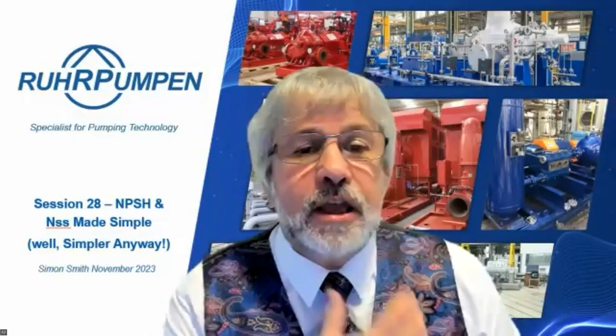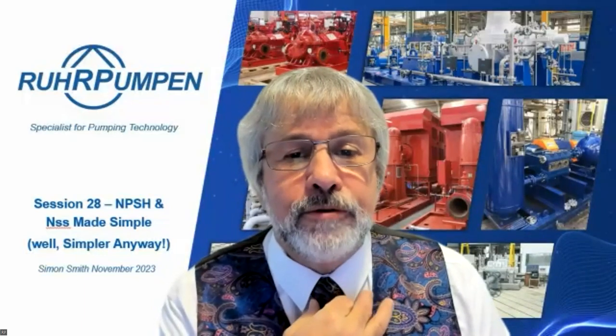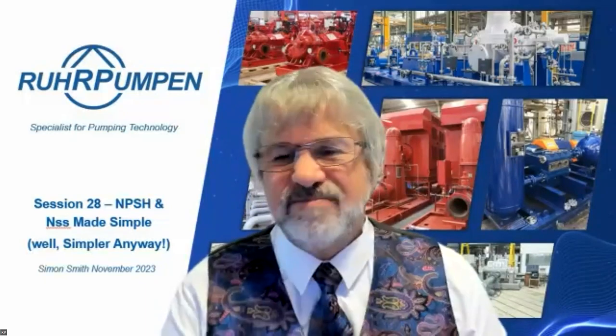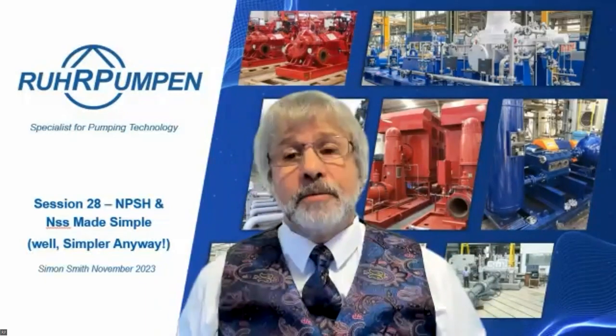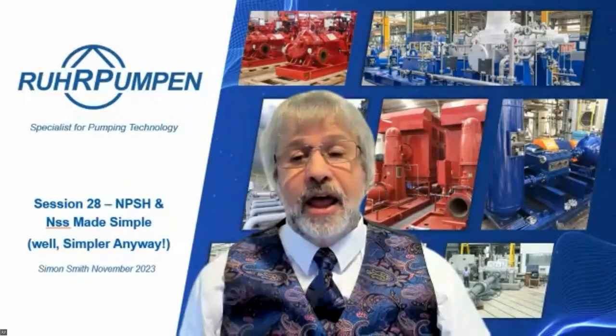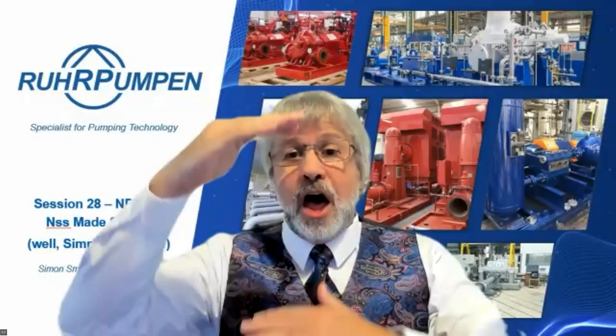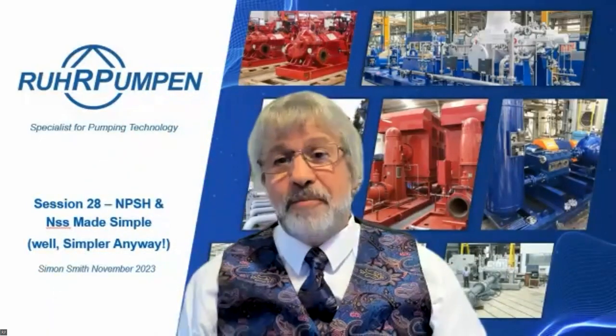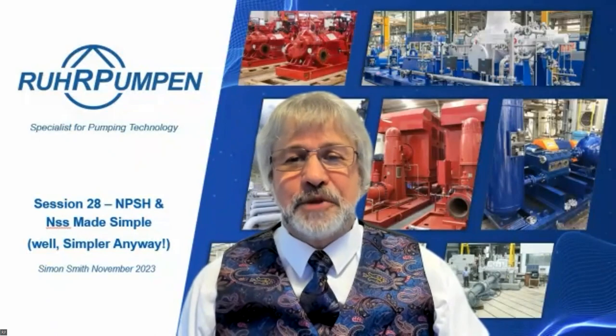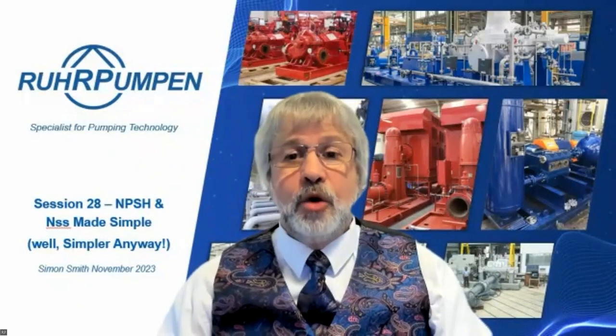Dharmesh Kumar Panchal asks about NPSH ratio versus NPSH margin. It's just two different ways of looking at the same thing. What we're looking for is to keep a nice healthy margin above the NPSHr. The more damaging the fluid - water being the worst possible case - the more margin you want. Whether you express that as a factor or as a number of meters of safety margin is up to you. The effect is the same: keep a big separation, especially with water.